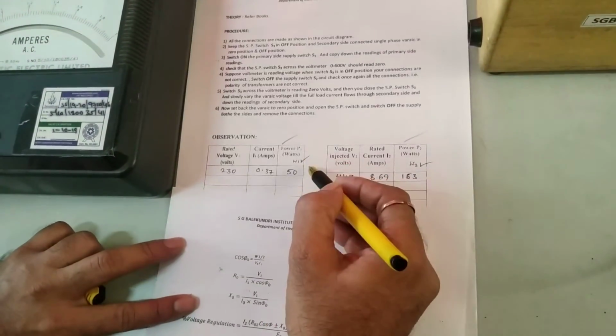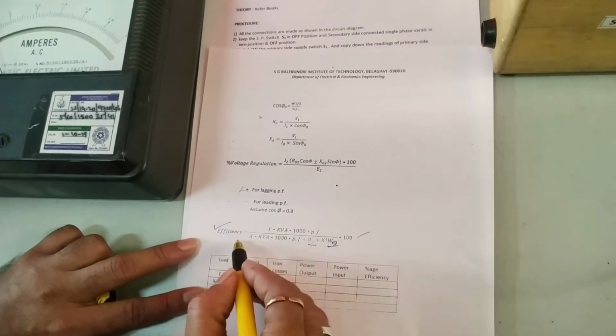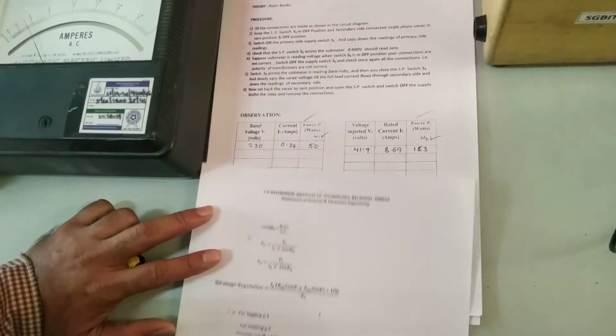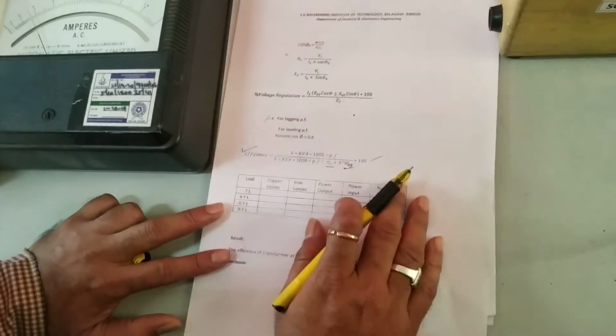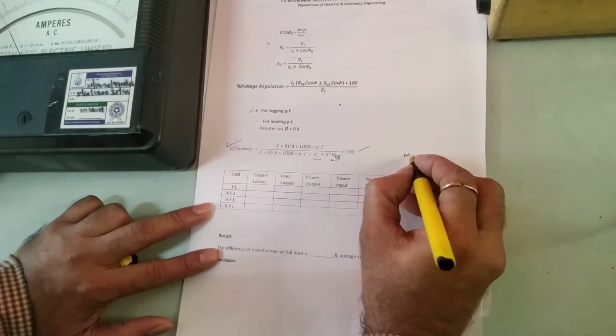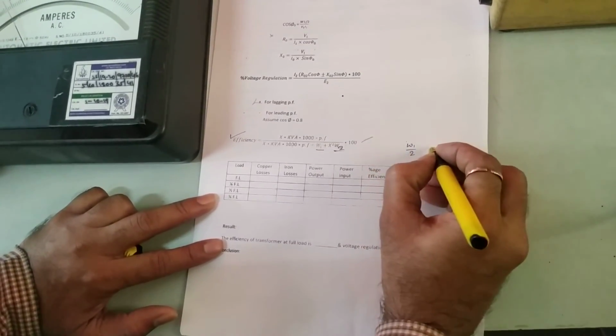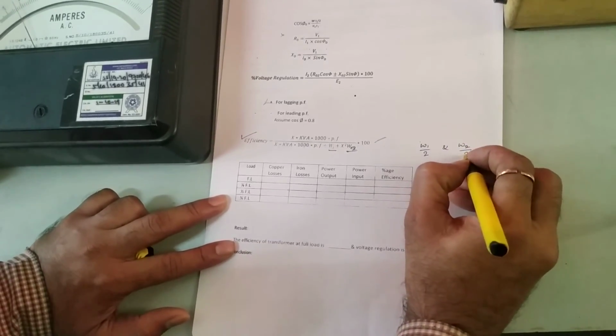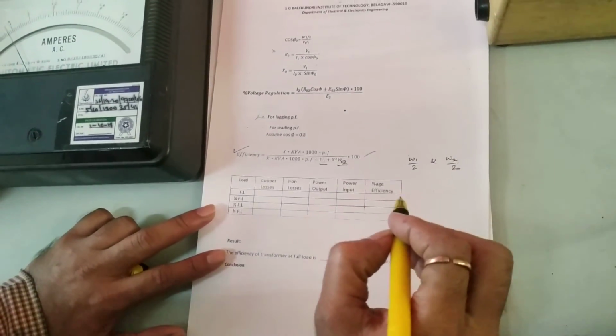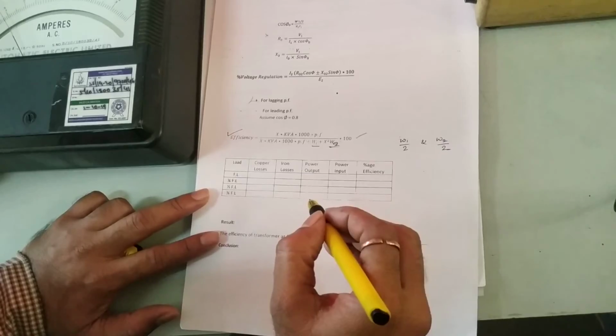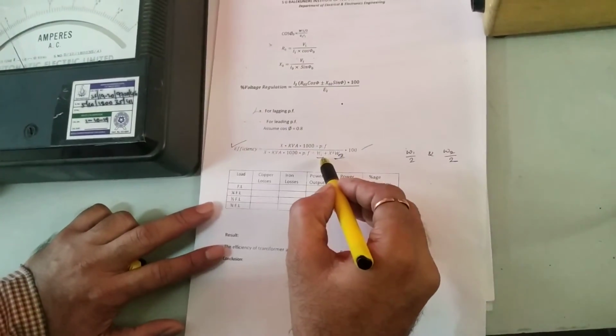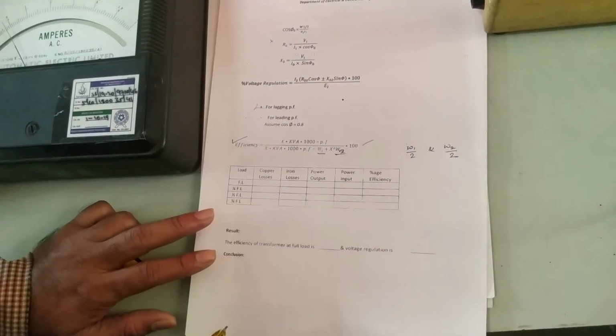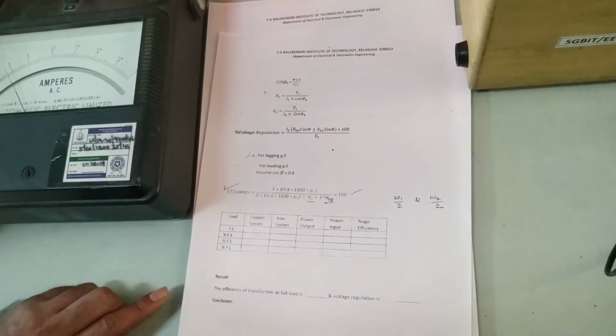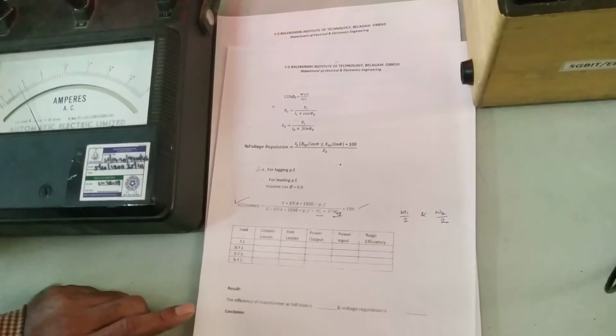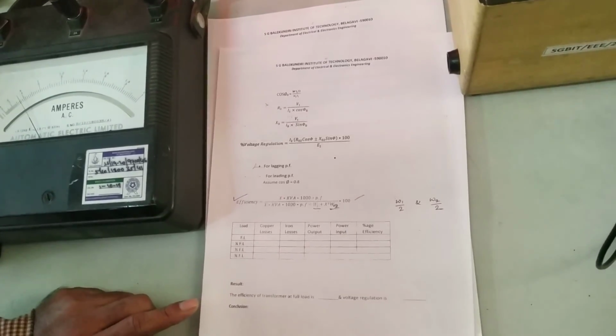If you take W1 and W2 values directly and substitute in this formula, the calculated efficiency is nothing but the efficiency of the combined transformer. If you want to calculate the efficiency of an individual transformer, then instead of W1 we should take W1 by 2, and instead of W2 we should take W2 by 2 for the individual transformer efficiency calculation. If you want to calculate combined efficiency, we need to take W1 and W2 as iron loss and copper loss respectively. So like this we can calculate the efficiency of the individual and combined transformer by conducting the Sumpner test on two similar single phase transformers.